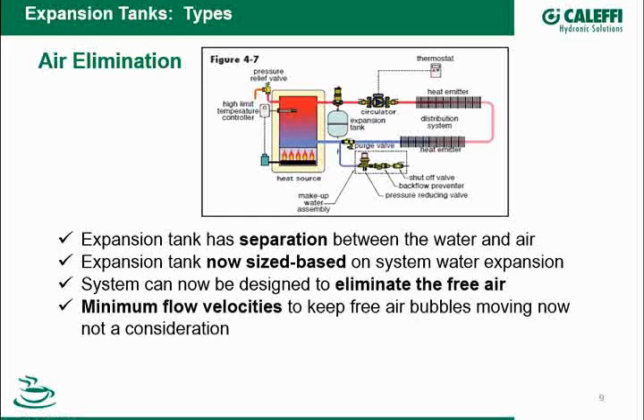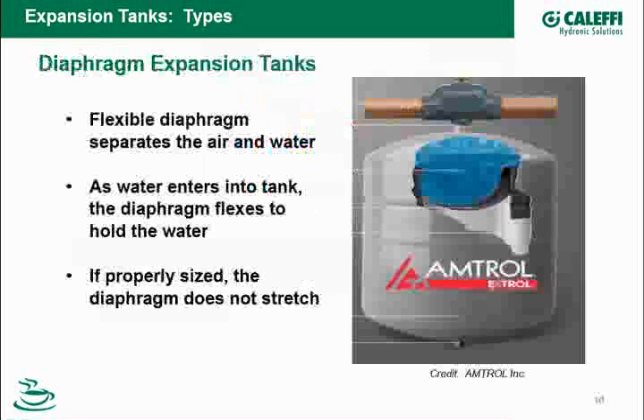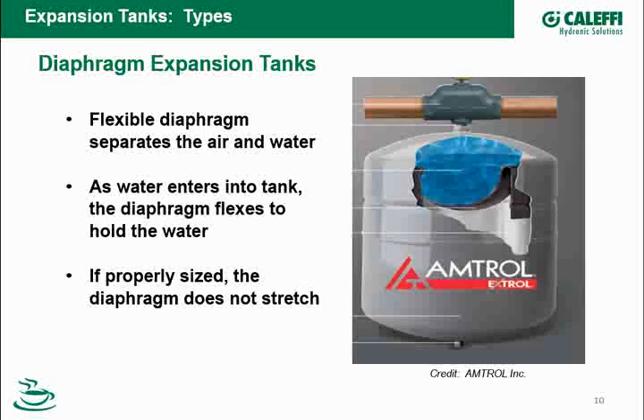Now, when it comes to expansion tanks, they usually are one of two separate designs, either a diaphragm tank or a bladder tank. We'll first look at the diaphragm tank. Typically, I would say probably the bulk of what we see on the residential side is primarily diaphragm tanks. If I look at this cutaway that was provided by Amtrol, it's showing here's my tank, and then the black here is a flexible diaphragm. So the diaphragm sits in there. When there's no water, the diaphragm is up against the top of the tank. As water comes in, it goes in between the tank and the diaphragm, and then it inverts the diaphragm and flexes into the tank itself and holds the water.